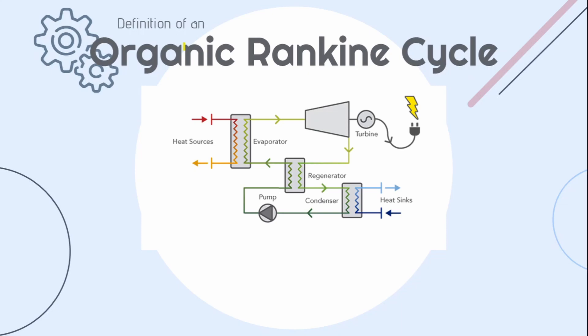Instead of generating steam from water, the organic Rankine cycle system vaporizes an organic fluid characterized by a molecular mass higher than that of water which leads to a slower rotation of the turbine, lower pressures, and no erosion of the metal parts and blades.